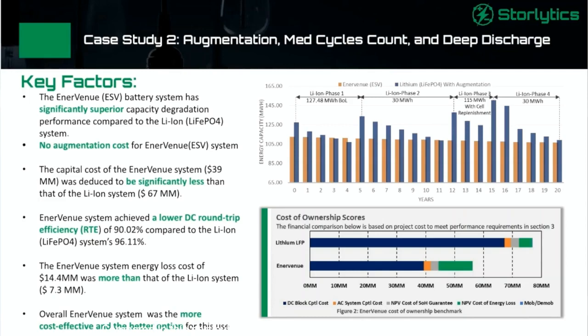But compare in this particular case, we were doing 3 augmentation cycles. So we started with 127.5 megawatt hour, so around 25% overbuilt for lithium. Around year 5, we needed to add some more capacity to maintain more than 100 megawatt hour, so we did around 30 megawatt hour of augmentation at phase 2. Then around year 12, we did a replenishment cycle.